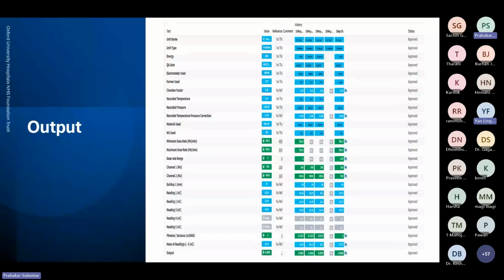So here you can see it is basically three readings. Basically three readings we are measuring, and then we are getting the output at the end. You can see what we have done for the last few months, and you can see different energies, and you can see the output, and you can set the tolerances. In the reference comment column, you can see the tolerances have been set. It should ideally be one, and you can set the tolerances how much you want to go with, depending upon the local protocols and policies.